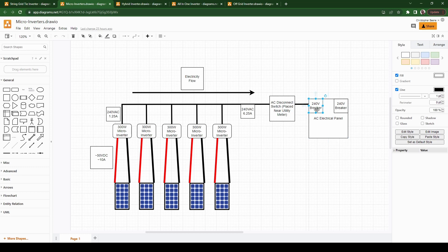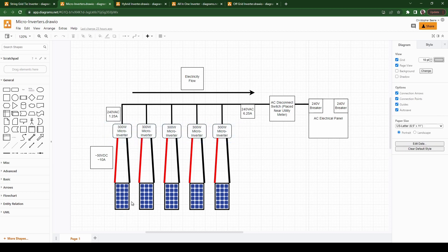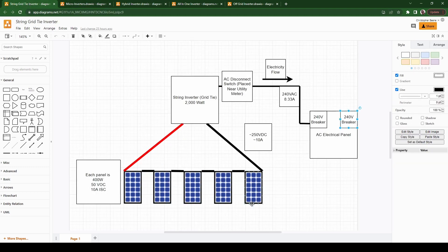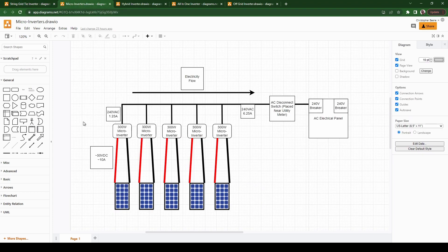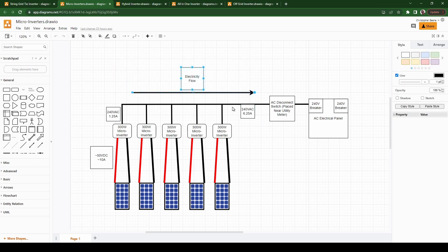Each panel has a DC connection up to the micro inverter and then you've got a trunk cable that plugs in just like an extension cord that runs all the micro inverters together back to the AC disconnect switch and into the electrical panel. You might have a 20 amp breaker here that can support 13 micro inverters all on one trunk line. If you wanted to add another line of panels you just do another 240 volt breaker. The big advantage to micro inverters is that if this panel here is shaded, none of the other panels care because the micro inverters are taking care of that DC to AC conversion.